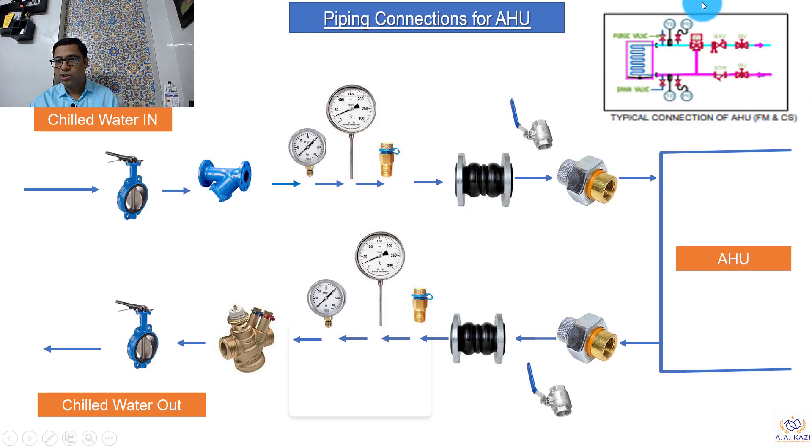This is how the piping connection looks. Looking at the chilled water inlet side: we have an isolation valve — this is a butterfly valve. Then we have a Y strainer, to remove particles or dirt from the water. Then we have a pressure gauge to see the pressure in this line, and a temperature gauge to see the temperature of water coming in. Test points are also provided — these can be used for BMS-related points, or if you cannot fit a pressure gauge or thermometer, you can plug in a separate instrument. Then we have flexible bellows to avoid vibration from the AHU to the pipes.